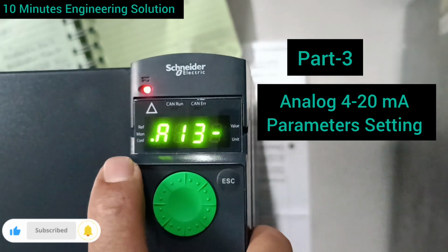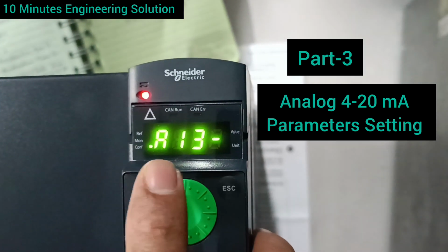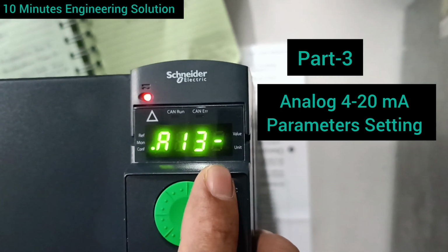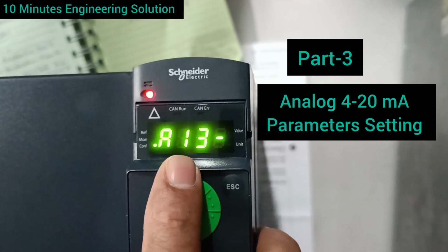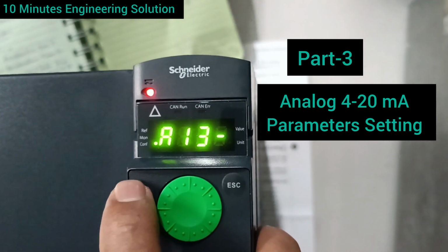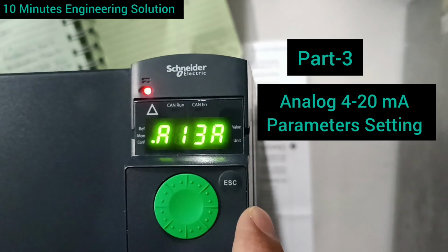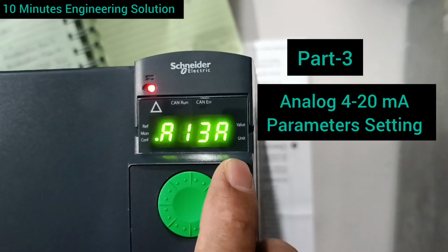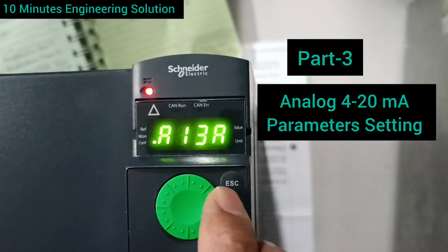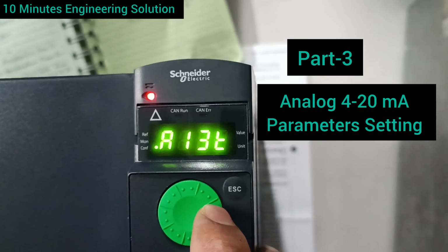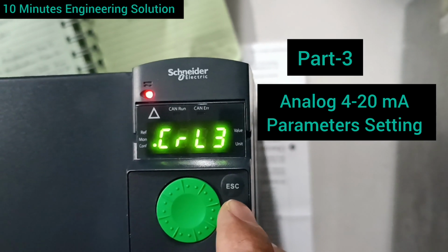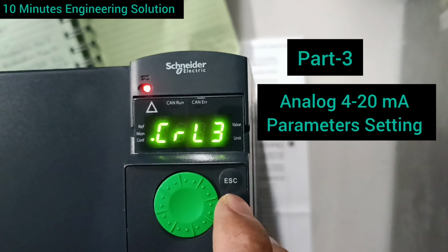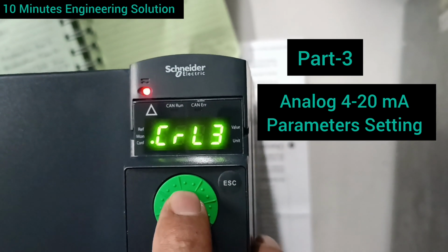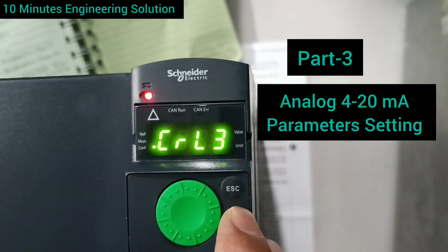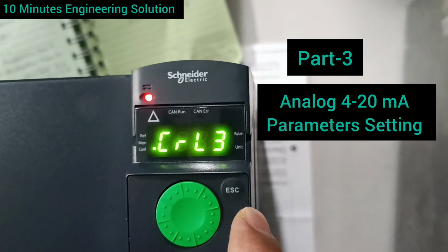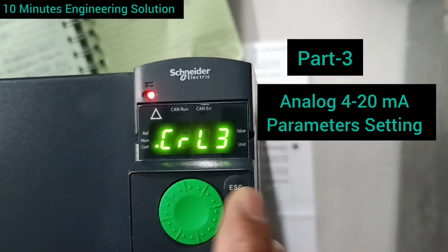This is the analog input setting. Later I'll describe AI3 and the wiring connection for the 4 to 20 milliampere connection. So this is the AI3 analog, and then scroll to CRL3. CRL3 means the minimum current setting. We need to set 4 milliampere.